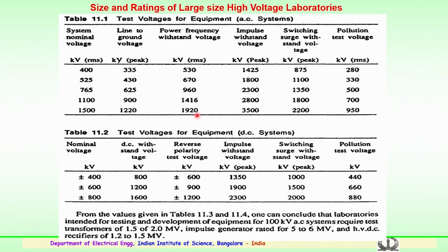Again, the withstand could be for a minute or 5 minutes. Again, this is dependent on the instructions or the standard procedures to be followed. So, impulse withstand, again for a 400 kV system the impulse withstand level will be 1425 kilovolts, and in case of 1100 kV it is 2800, and in case of 1500 kV it is 3500 kV. For switching surge, again lightning impulse withstand is 1.2 by 50 microseconds.